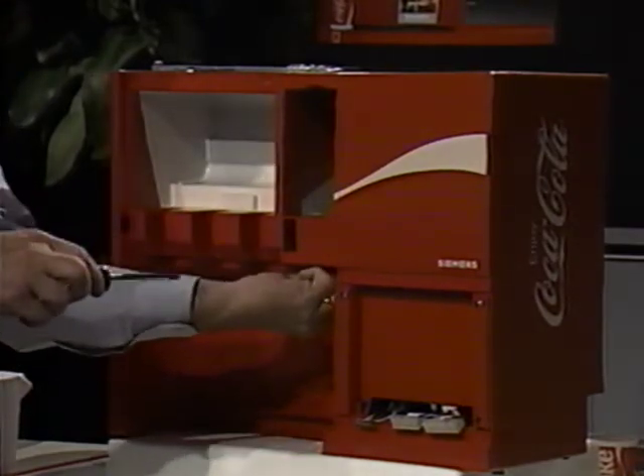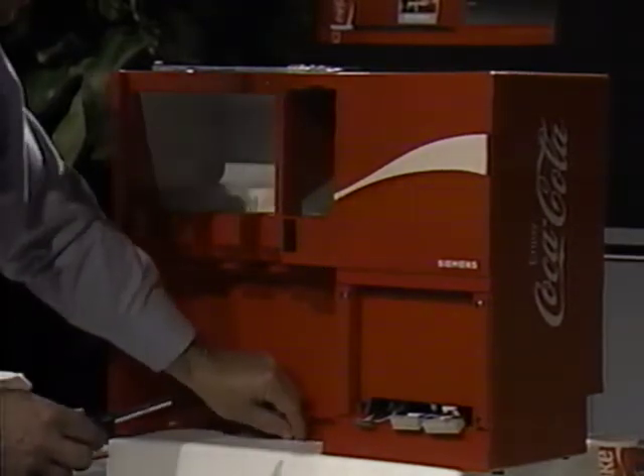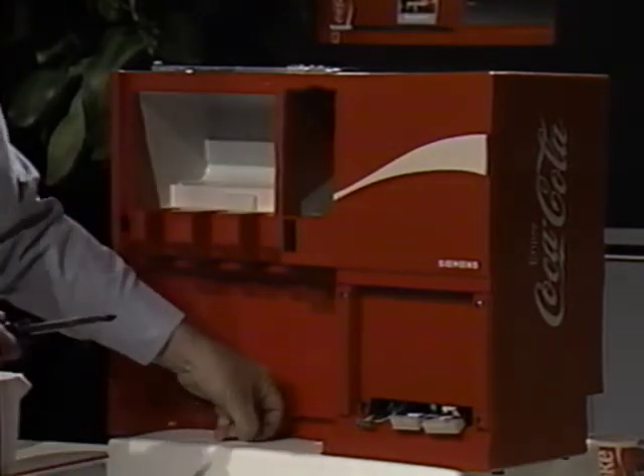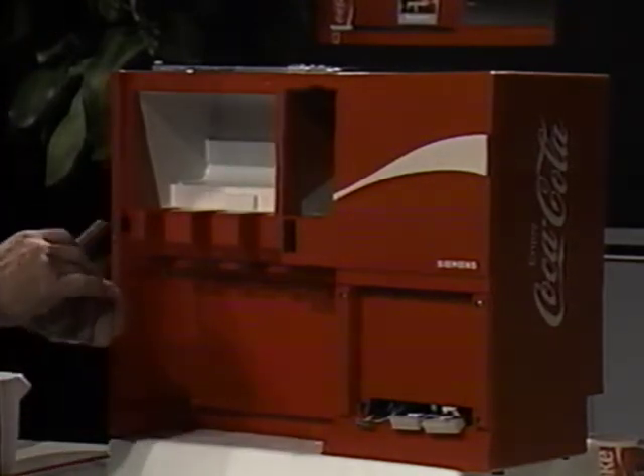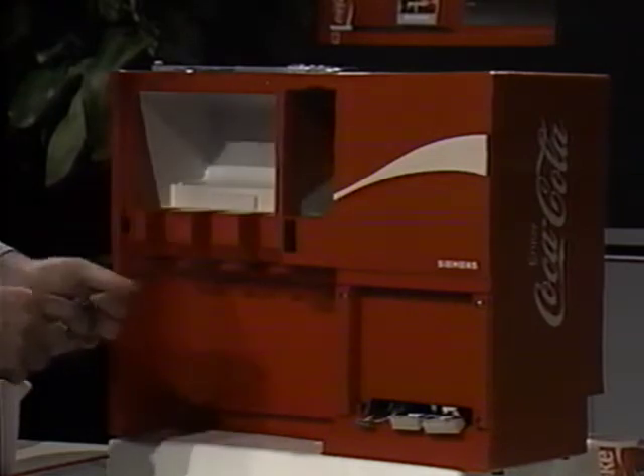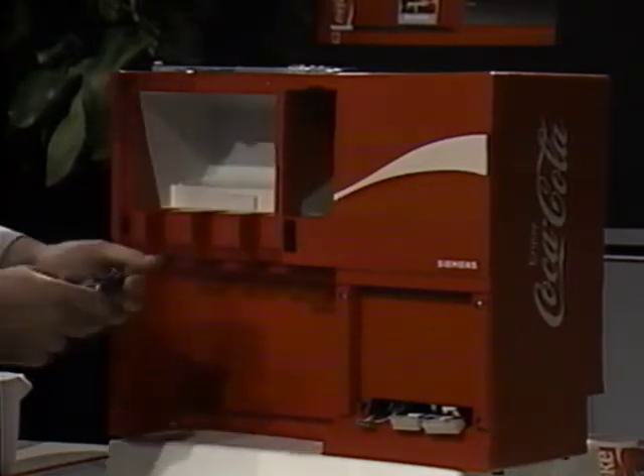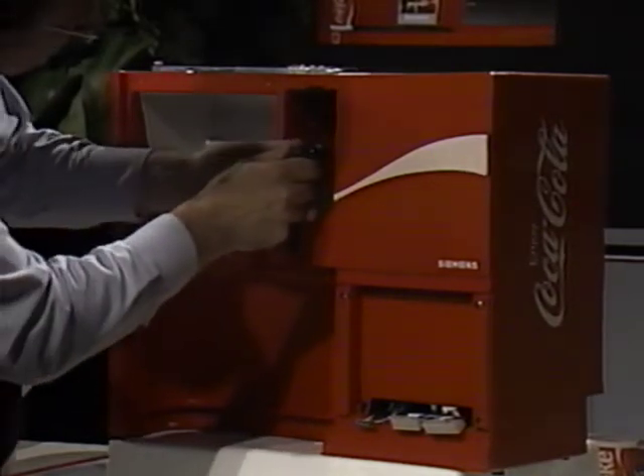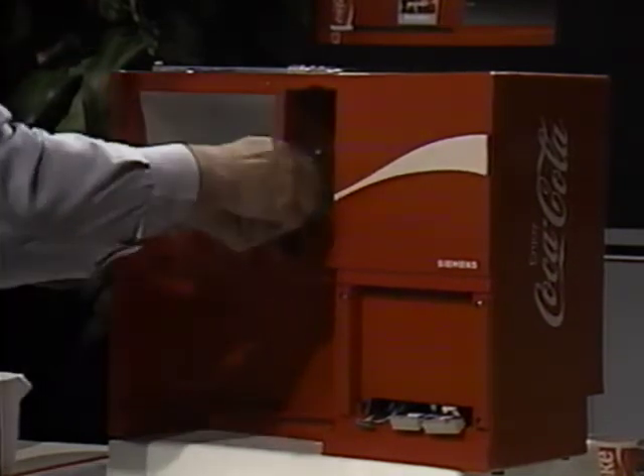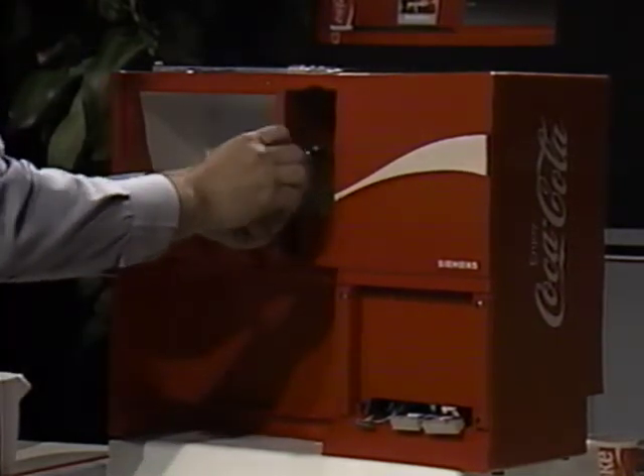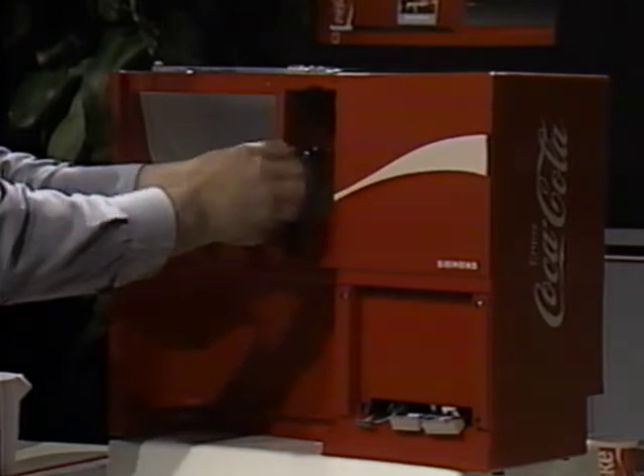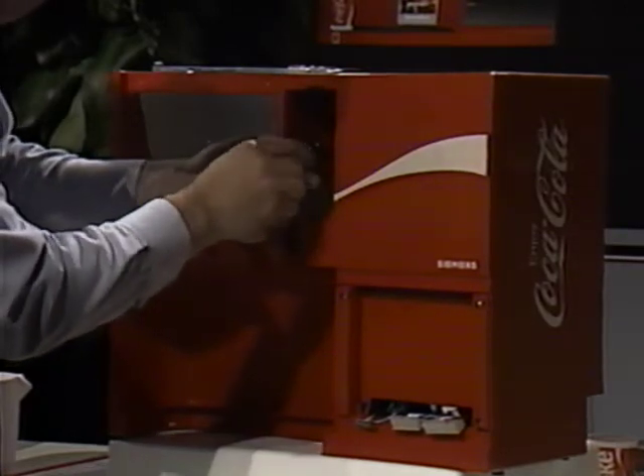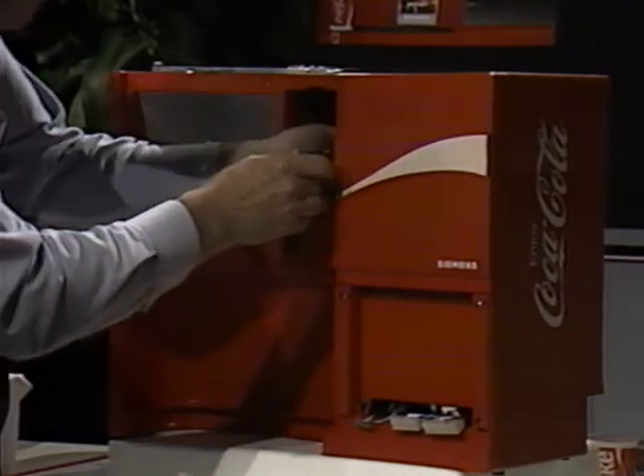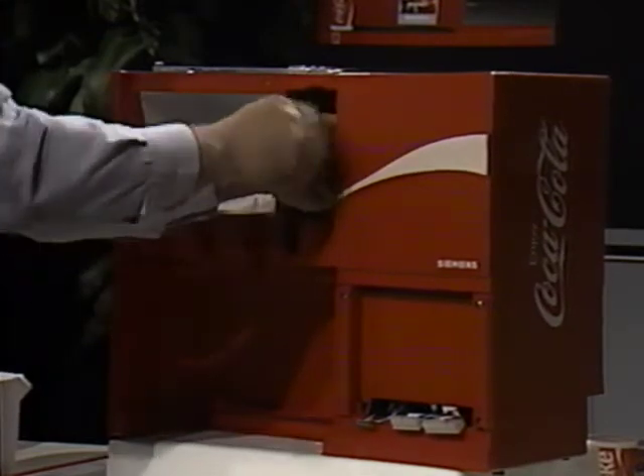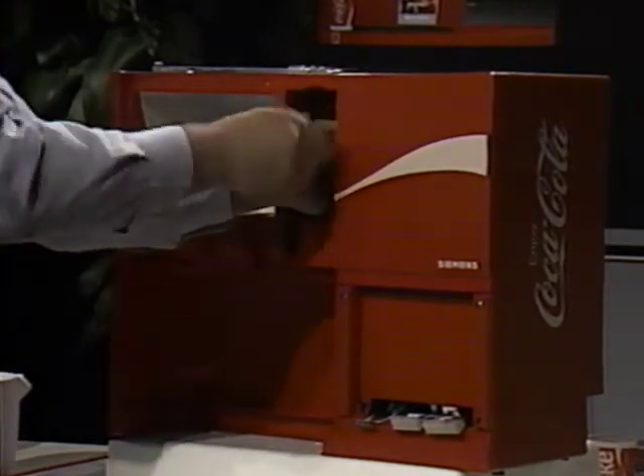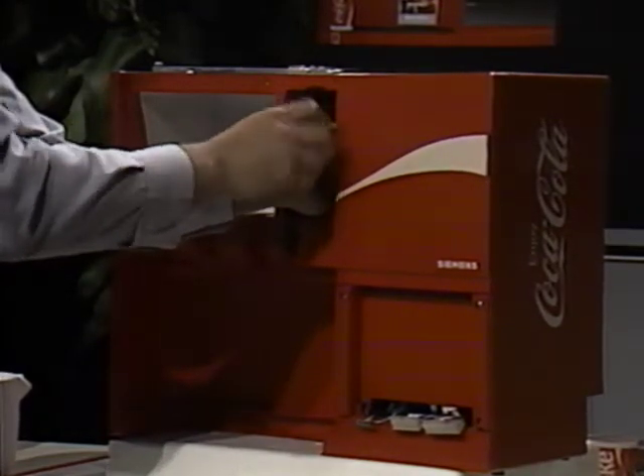The order of taking them out is not important, but the order of putting them back is somewhat important. You should put these 2 screws in first and then this screw in next to be sure you don't drop a screw down in the CO2 well and have it fall down inside the machine. I use a magnetic screwdriver because it holds onto the screws and lifts them across.